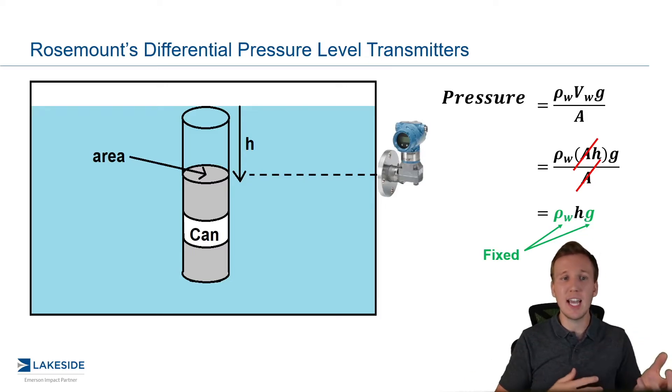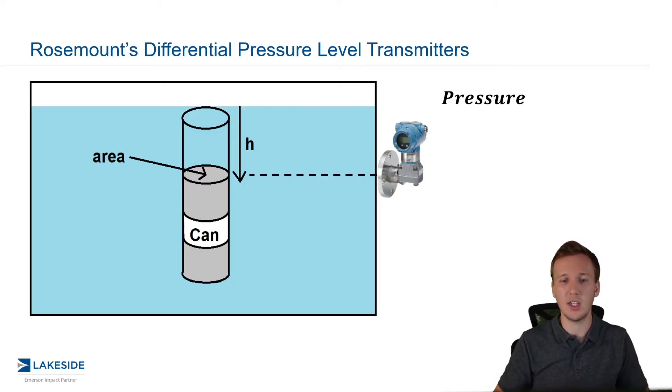But the reality is density does change over time with pressures and temperature changes. And as we talked about in the limitations video, this is one of the big limitations or drawbacks of a DP level transmitter is we have to assume this is constant. But nevertheless, let's assume that is a good assumption and let's continue on with our equation here.